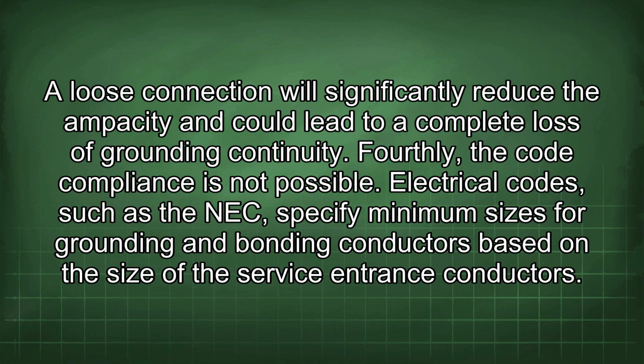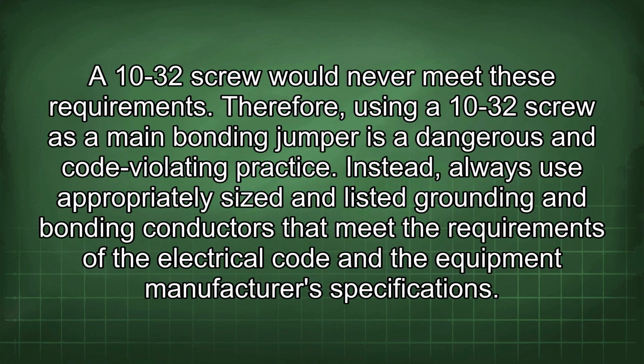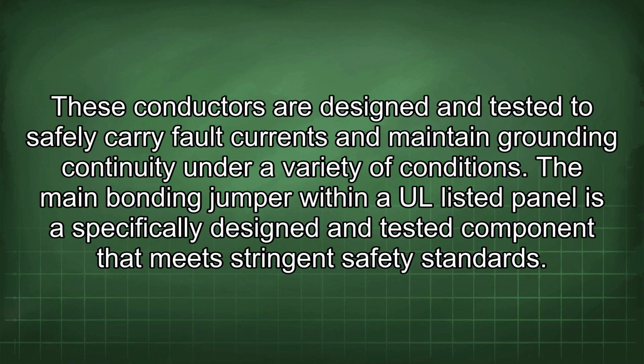Fourthly, code compliance is not possible. Electrical codes, such as the NEC, specify minimum sizes for grounding and bonding conductors based on the size of the service entrance conductors. A 10-32 screw would never meet these requirements. Therefore, using a 10-32 screw as a main bonding jumper is a dangerous and code-violating practice. Instead, always use appropriately sized and listed grounding and bonding conductors that meet the requirements of the electrical code and the equipment manufacturer's specifications. These conductors are designed and tested to safely carry fault currents and maintain grounding continuity under a variety of conditions.